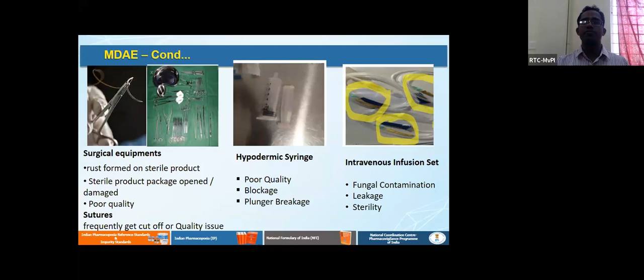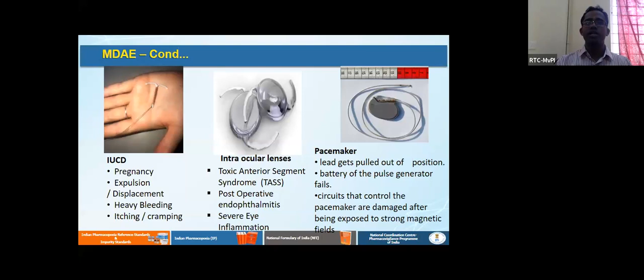And in intraocular lenses, things like TASS syndrome or postoperative endophthalmitis or severe eye inflammation are critical cases we monitor in a shorter time. We take the information to the manufacturer and the regulators to resolve those things. And for the pacemaker, we can find the lead pulled out of position, or the battery or pulse generator fails, or the circuit that controls the pacemaker gets damaged after being exposed to strong magnetic fields. They are usually checked at regular intervals, but still some issues may be found, or the battery may go off before the described time.